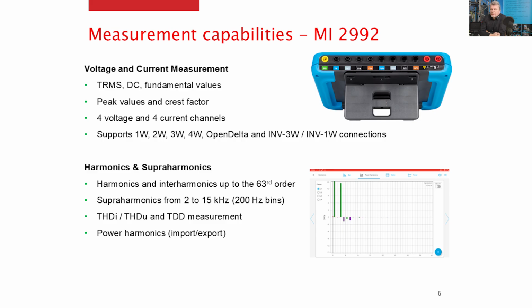Regarding the harmonics, we make a step forward. We are measuring harmonics and interharmonics up to the 63rd order, and also supraharmonics from 2 to 15 kilohertz with 200 hertz bins according to the standard. Which devices generate such supraharmonics? For example, photovoltaic inverters or electric vehicle charging stations. So you can monitor the main frequency of such equipment.